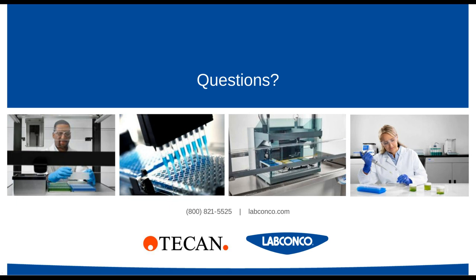And we have another question here. Well, this person's asking, what does biosafety enclosure mean? Yeah, good question. So the term is broad. When we're talking about a biosafety cabinet or a biosafety enclosure, we're talking about, at a minimum, something that protects the user. So it's going to be providing negative pressure airflow into the cabinet or enclosure to keep them safe.